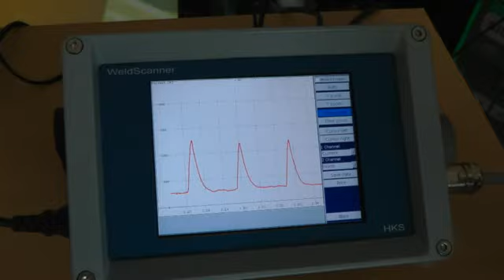Last but not least, function number 3 of the weld scanner is the so-called calibrator mode, or calibration mode. In calibration mode, the system works as a calibrator, meaning you can calibrate your welding equipment and welding machines using our weld scanner and sensors.